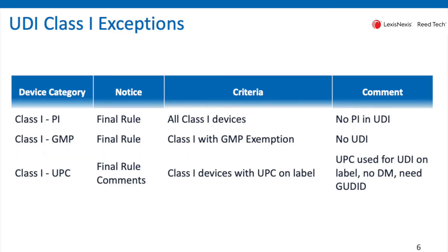Since the Class 1 compliance date has not occurred yet — looking to next year — I thought I'd include a couple of very specific notes on Class 1 products. Those manufacturers of Class 1 medical devices: if you find that your Class 1 product has a good manufacturing practice exemption — a GMP exemption, not referring to a 510 exception — roughly 15–20% have a GMP exemption. If you find that is true, you have no UDI requirements.